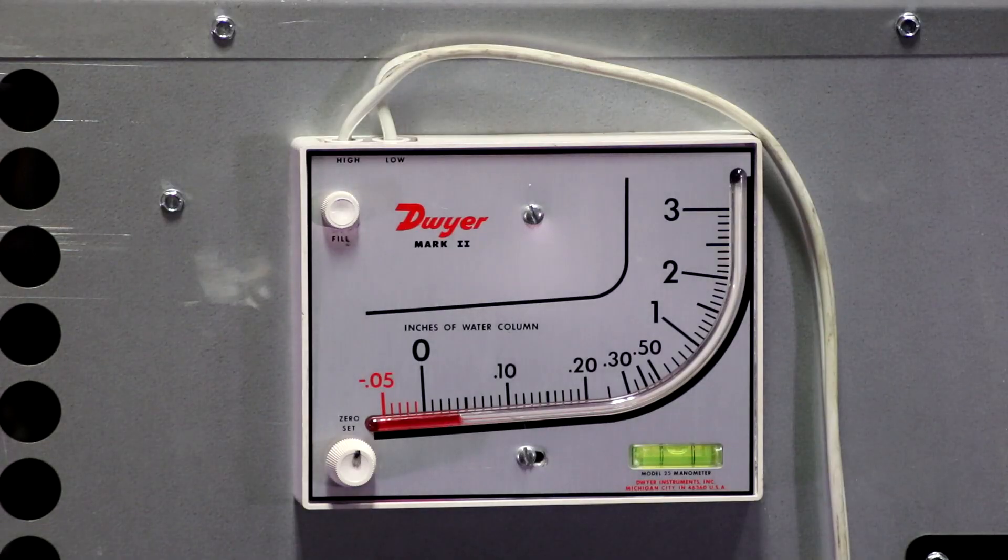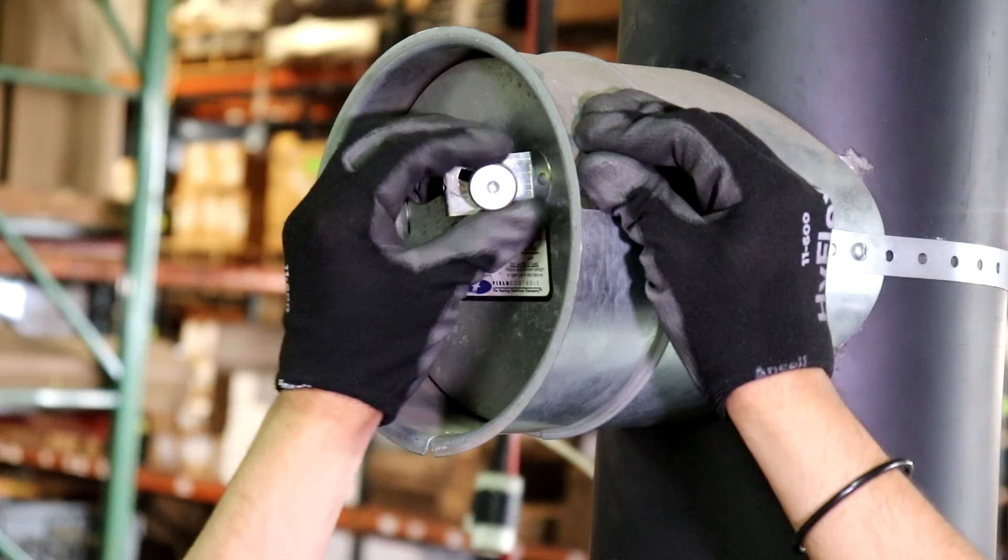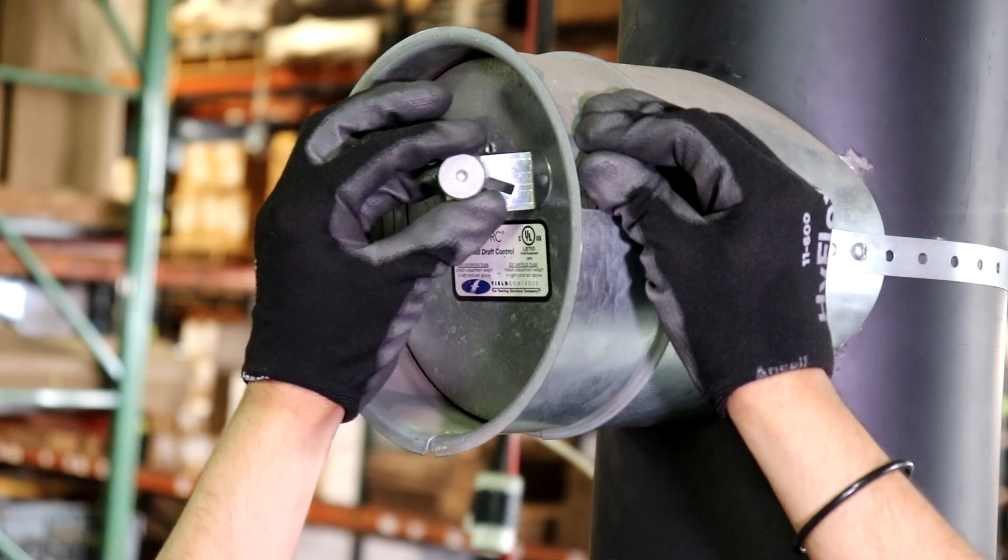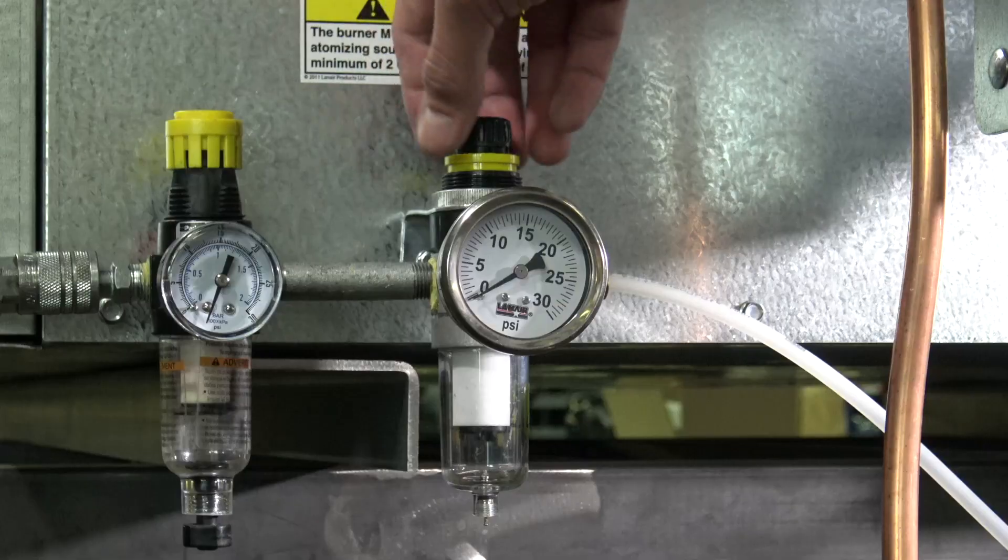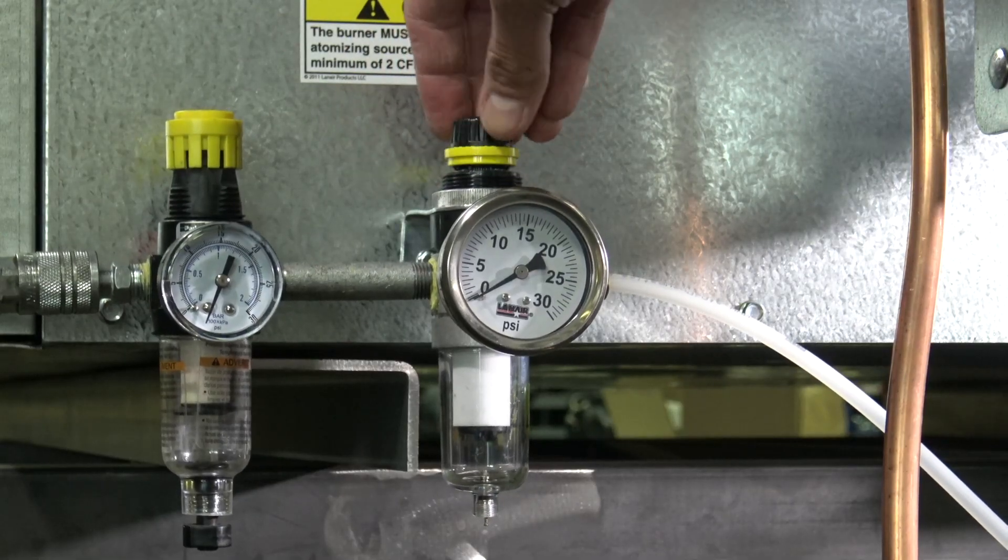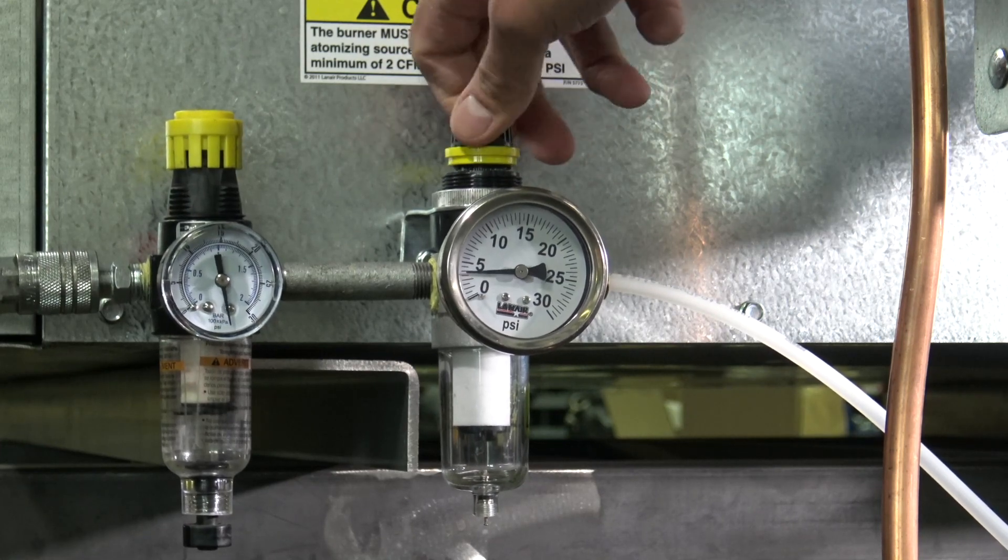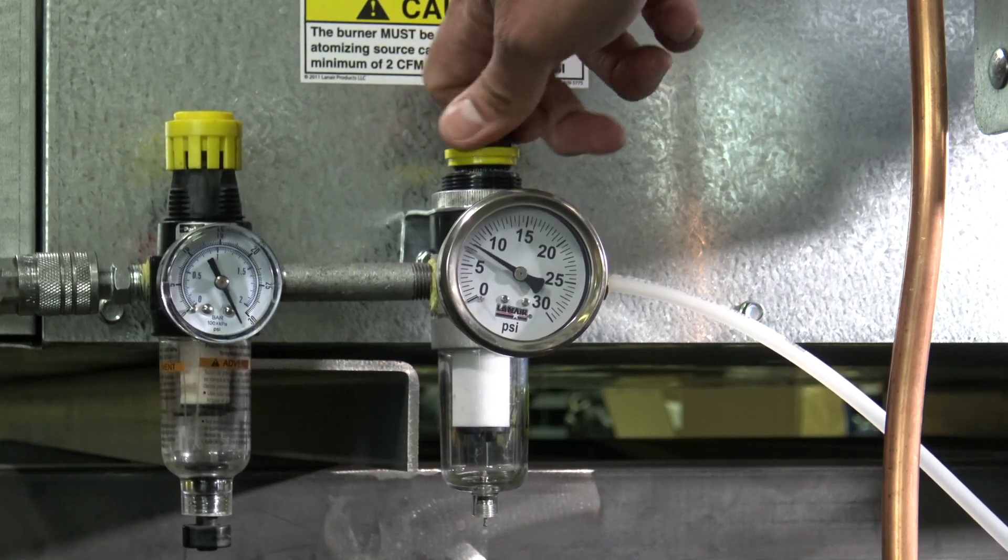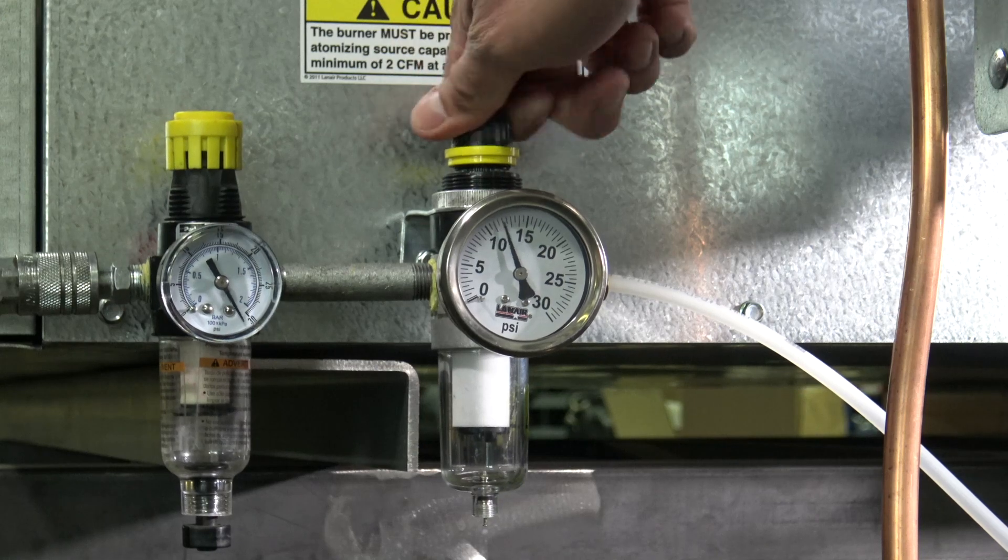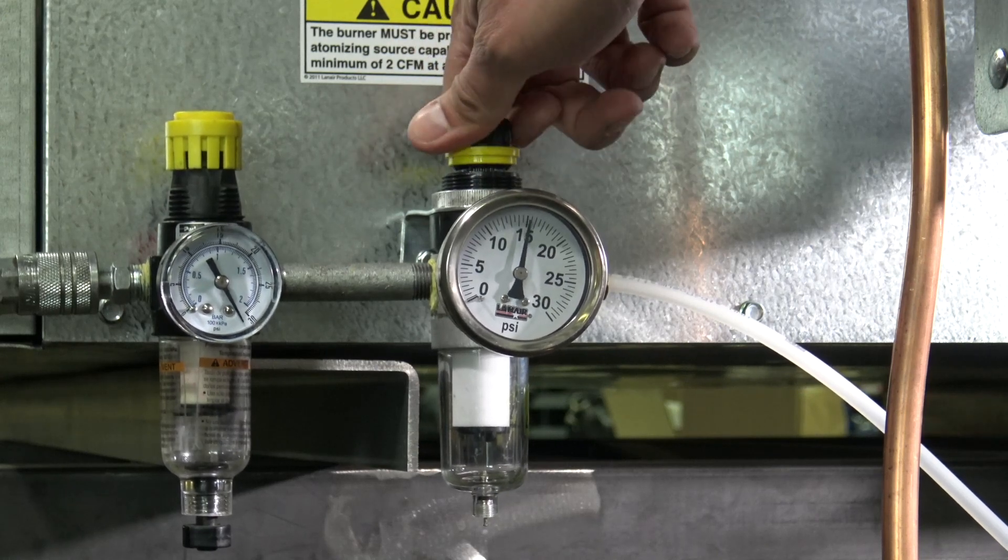When the unit has reached operating temperature, check the chimney draft to ensure that it is correct according to the product instruction manual. If necessary, use a gloved hand to adjust the damper door in order to achieve proper draft. Ensure that the primary air pressure regulator is supplying 30 psi to the secondary air pressure regulator, and that the secondary air pressure regulator is supplying the appropriate initial air pressure setting to the unit, based on the product instruction manual's recommendation for your model.